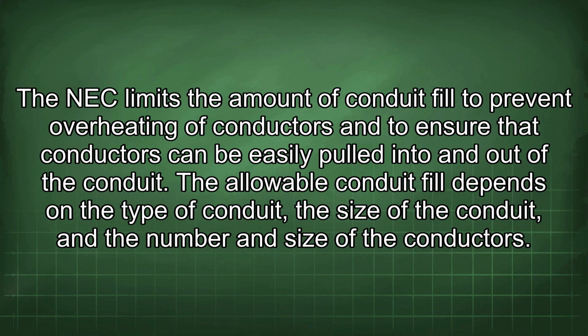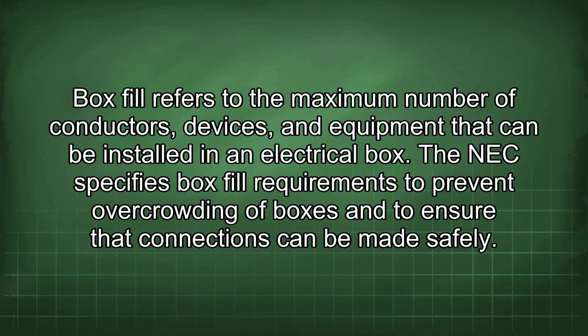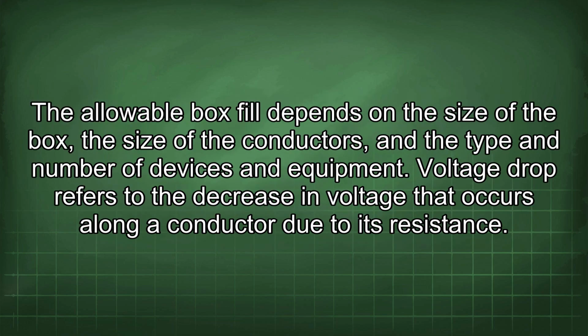of the conductors. Box fill refers to the maximum number of conductors, devices, and equipment that can be installed in an electrical box. The NEC specifies box fill requirements to prevent overcrowding of boxes and to ensure that connections can be made safely. The allowable box fill depends on the size of the box, the size of the conductors, and the type and number of devices and equipment.